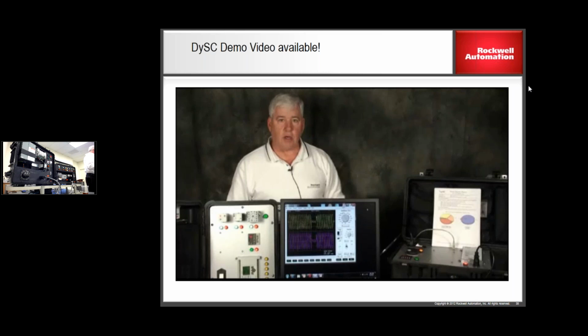That relay shouldn't have popped. Maybe it's a safety gate, and somebody walked through it. For goodness sakes, the PLC is going to take action and shut you down. Then you come up and investigate, look in your PLC, and say, Charlie, why'd you walk through the gate? Because you're not going to think it had anything to do with power. The lights didn't blink, it's only 2 cycles long. It couldn't have been power, it had to be Charlie. Or it's a broken machine, so we better go fix it, right?